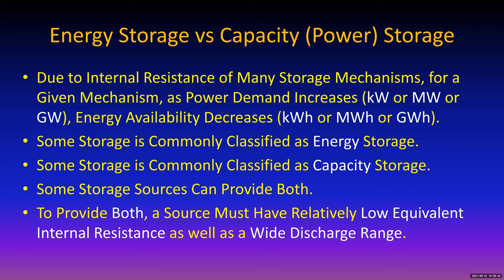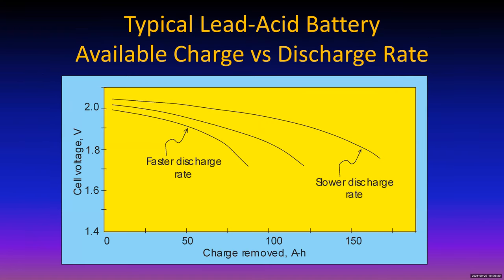Just some useful pieces of information about energy storage if we're going to get serious about building some. Here's what happens with lead acid batteries: the faster you discharge them, the faster they run out of charge, so the fewer amp hours you get from the battery, because you warm up the battery faster. The current squared times the internal resistance of the battery is the heat produced within the battery, which is not available for operating any external load.